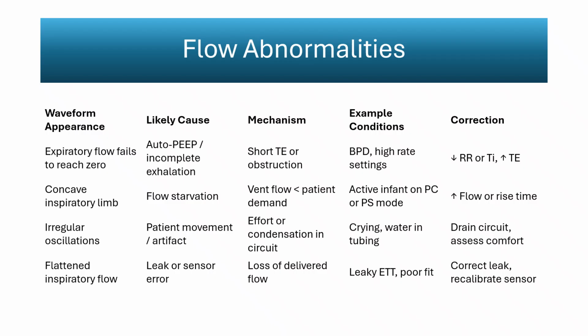When a significant leak is present, around an uncuffed tube or at a poor circuit connection, the ventilator cannot generate or measure normal inspiratory flow, so the curve becomes blunted. Sensor issues, such as a misaligned or contaminated proximal sensor, produce the same appearance by undermeasuring the true flow. Correction involves identifying and repairing the leak, and recalibrating or replacing the flow sensor if needed. Together, these flow patterns illustrate how airway mechanics, ventilator settings, and circuit integrity shape each breath. Recognizing them quickly allows targeted corrections that restore efficient ventilation.